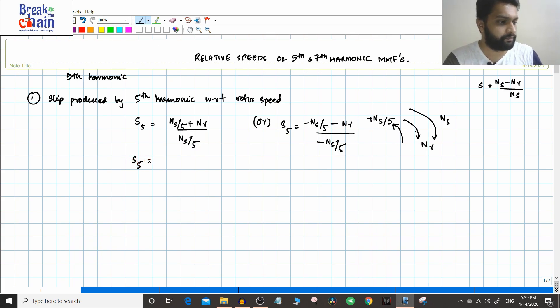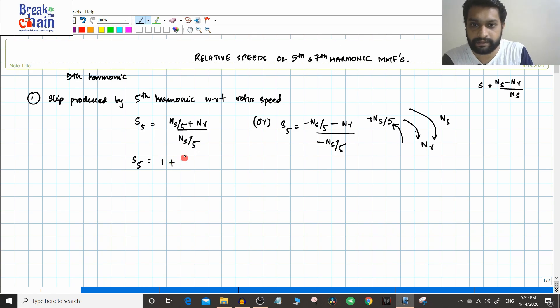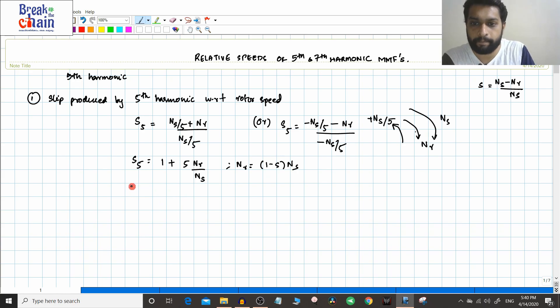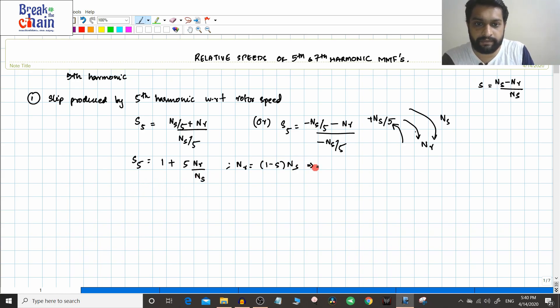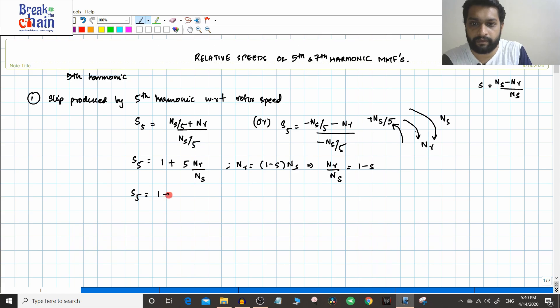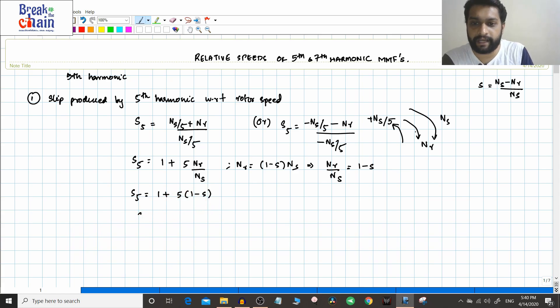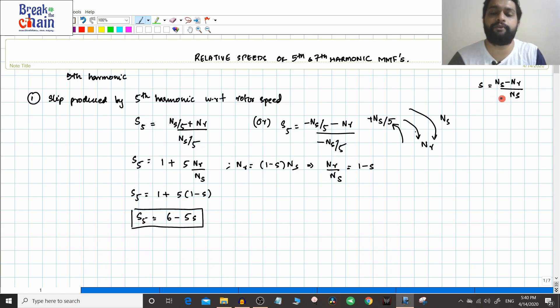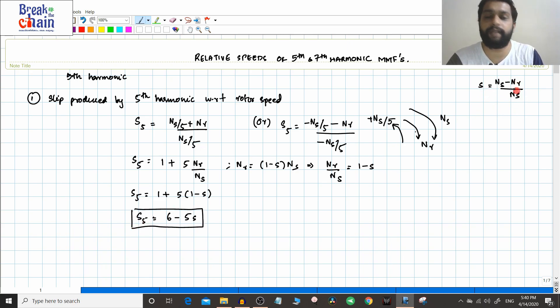So s5 equals 1 plus 5 times nr divided by ns. Since nr equals (1 minus s) times ns, we get nr/ns equals 1 minus s. Therefore s5 equals 1 plus 5(1 minus s), which gives s5 = 6 minus 5s. So if s is the fundamental slip, then 6 minus 5s is the slip produced by the fifth harmonic with respect to the rotor speed.